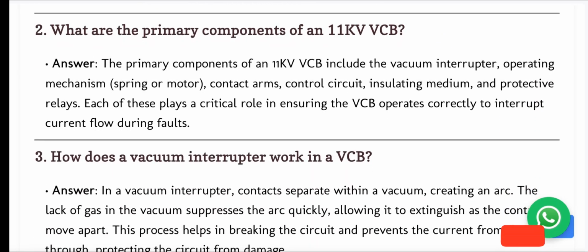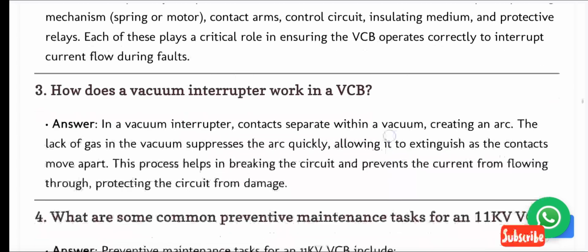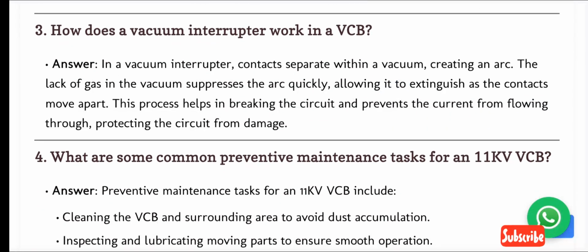Answer. The primary components of an 11 kV VCB include the vacuum interrupter, operating mechanism, spring or motor, contact arms, control circuit, insulating medium, and protective relays. Each of these plays a critical role in ensuring the VCB operates correctly to interrupt current flow during faults. 3. How does a vacuum interrupter work in a VCB?